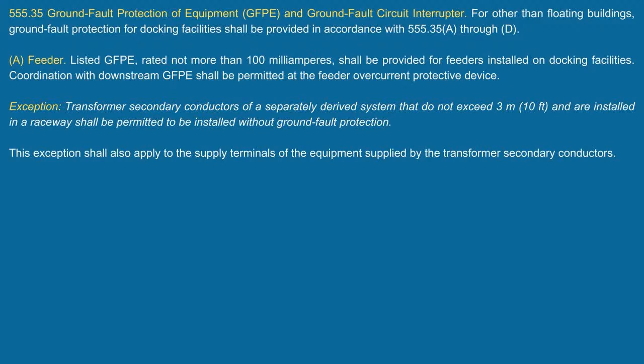All right, so you've got ground fault protection of equipment for the boat. You have GFCI protection for everything else. So here's my regular old receptacle, we would just follow the typical rules in 210.8(b). It's outdoors, it's got to have GFCI protection. But even if that rule didn't exist, this rule says outlets that don't supply shore power still have to have GFCI protection.